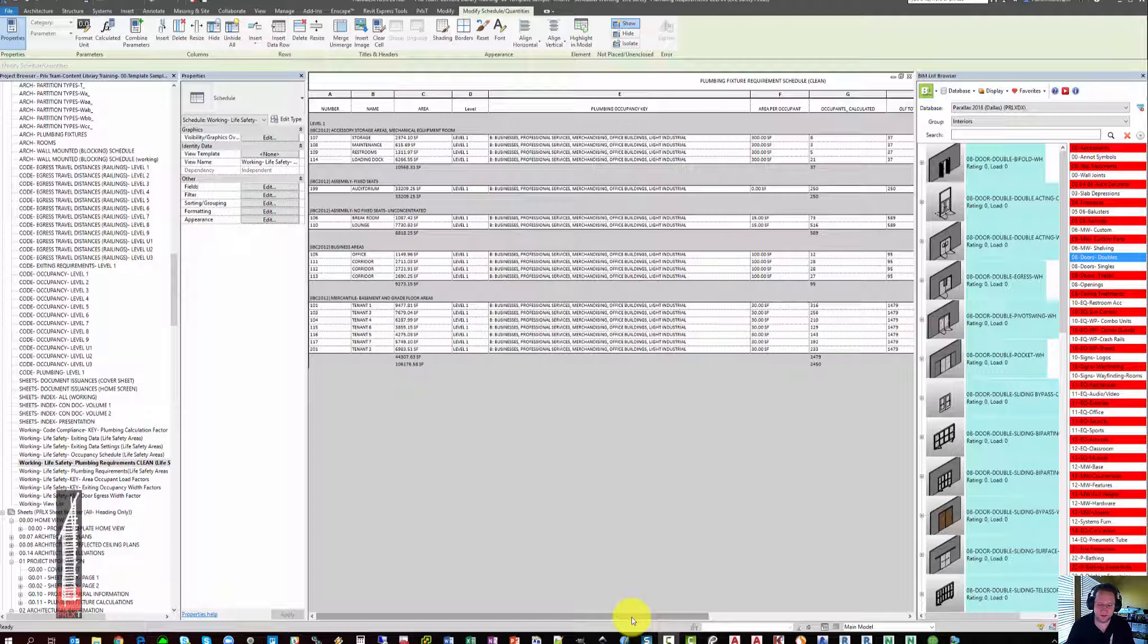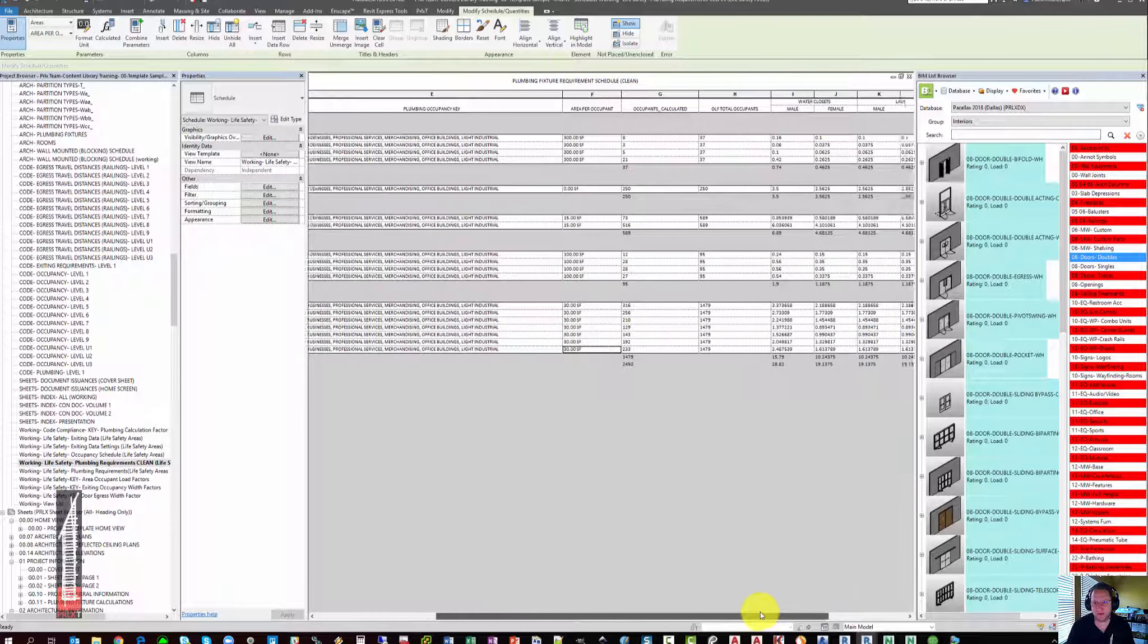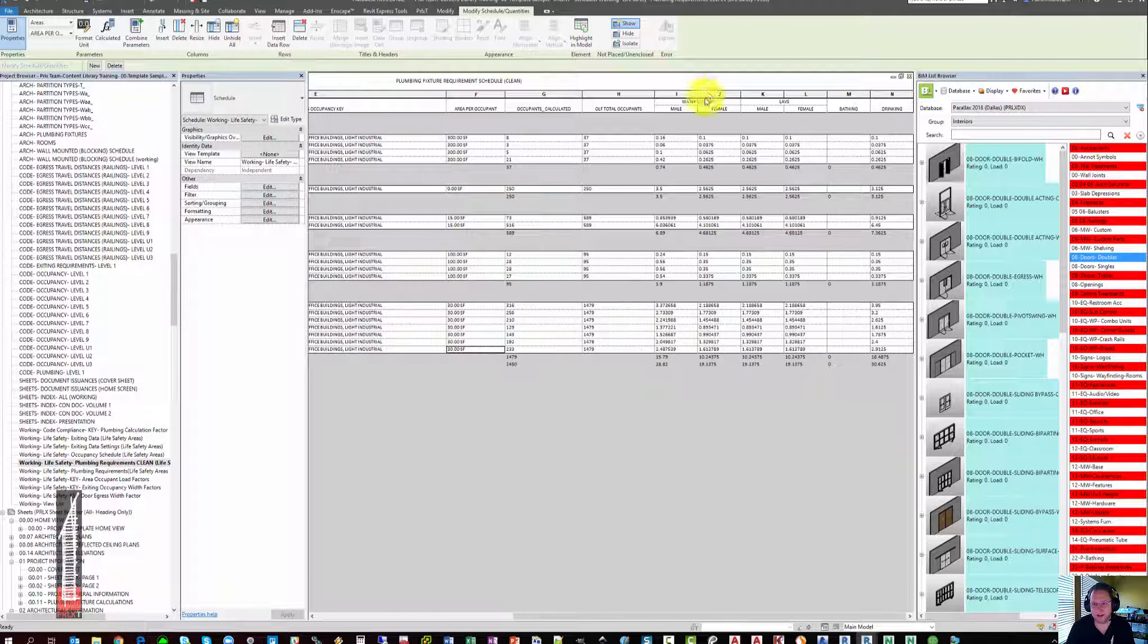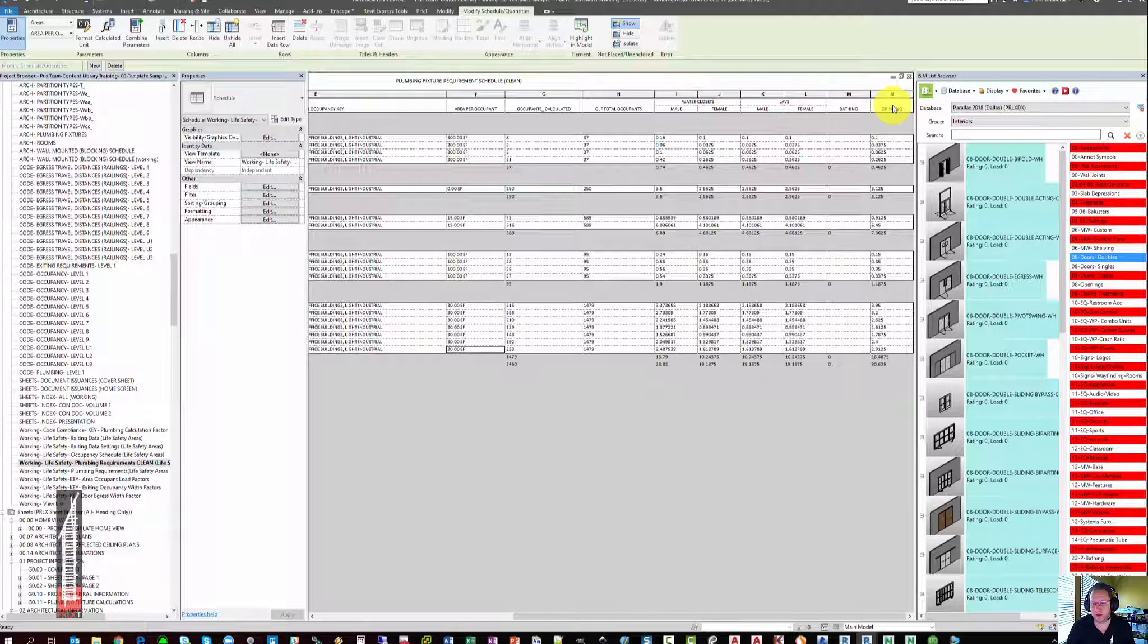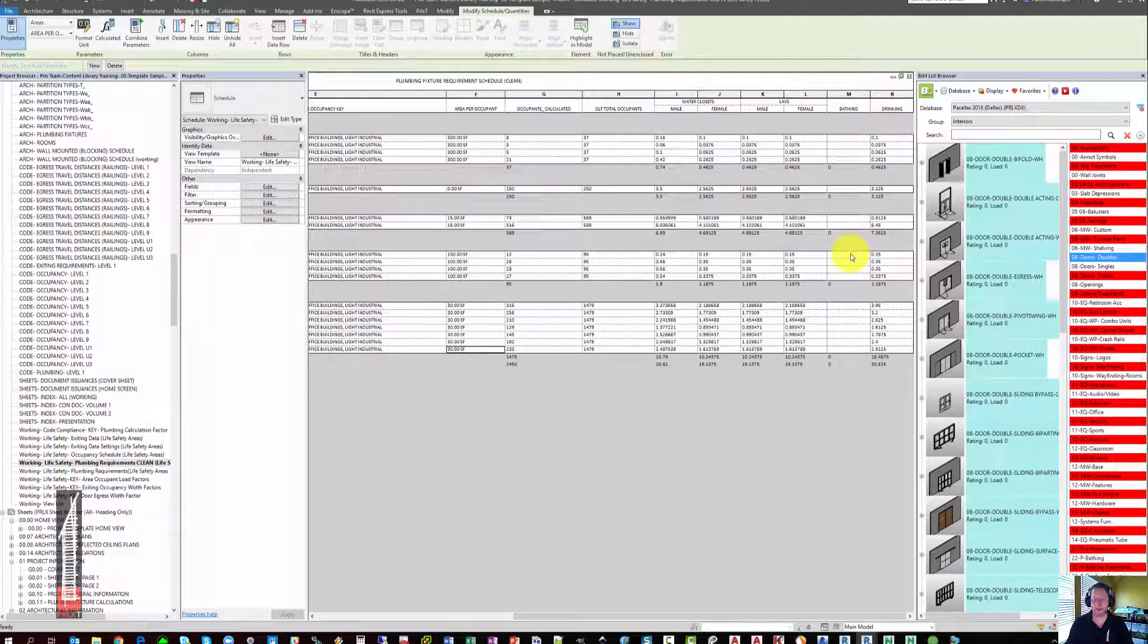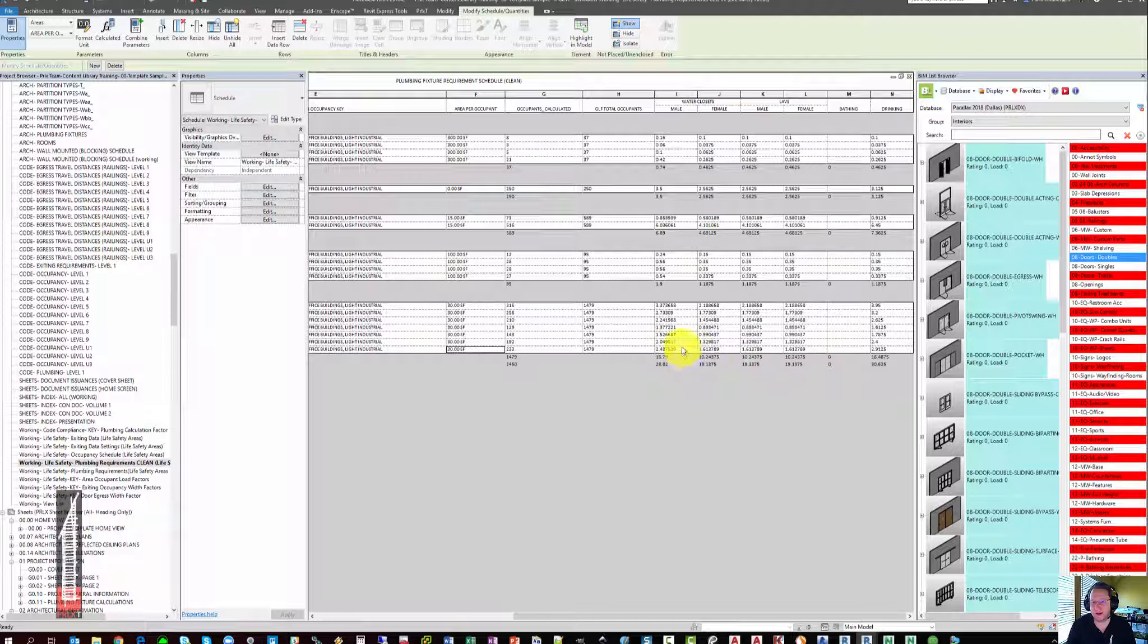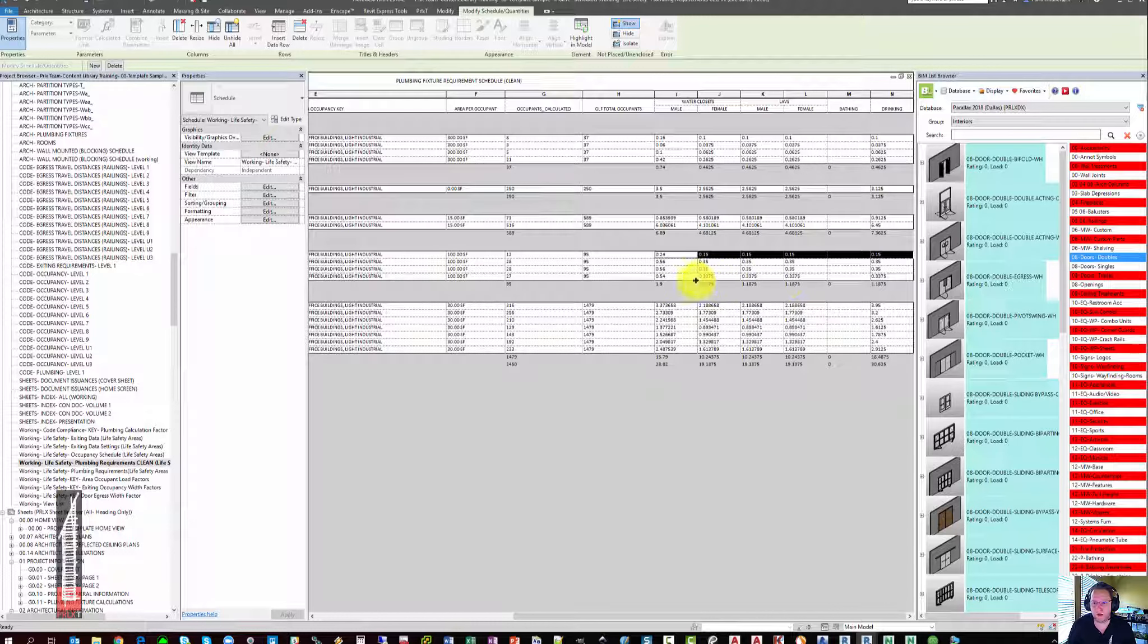And again, you can copy and paste throughout the schedule. Once you have everything filled in, you'll notice that if you slide to the right, the schedule is starting to calculate how many water closets, how many lavs, how many bathing units, and how many drinking fountains are needed for the project. You'll notice that the template keeps all of these values unrounded. I recommend leaving them unrounded. And then simply providing an additional schedule of plumbing fixtures in your project.